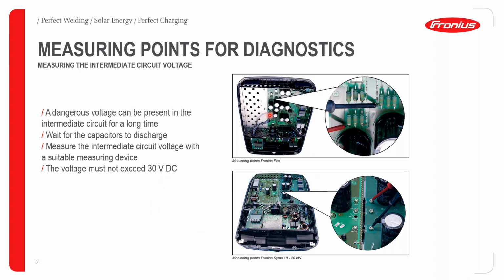Because of this, you need to measure these DC points before you unplug the AC board or the DC board from the inverter. A dangerous voltage can be present in the intermediate circuit for a long time, even if you disconnect your AC and DC, because the voltage comes from your capacitors. Remember, once disconnected from its power source, a capacitor can still hold a charge for a certain period of time.